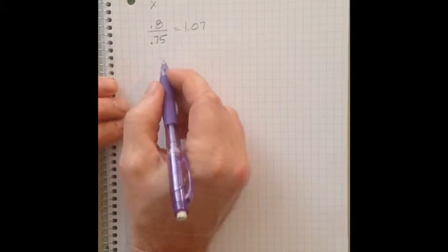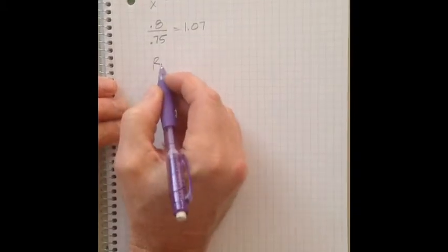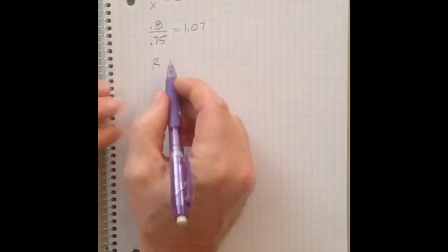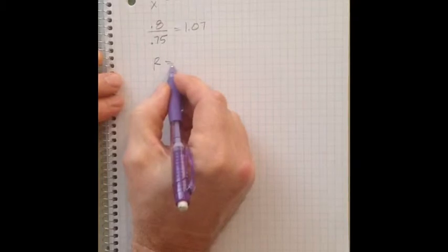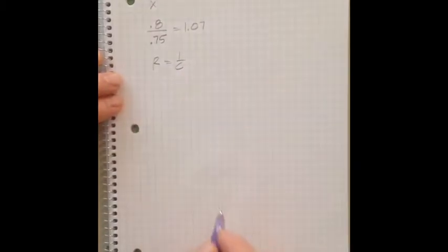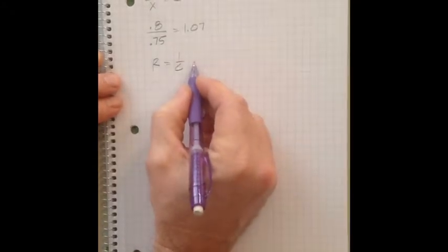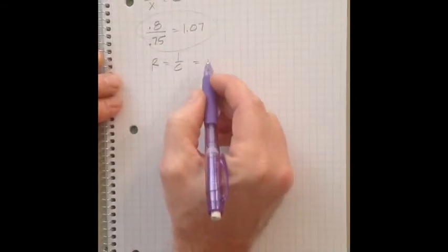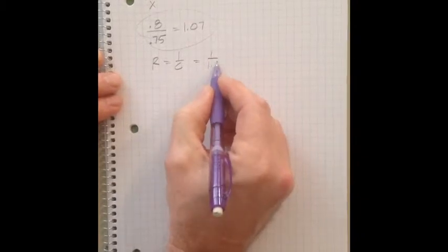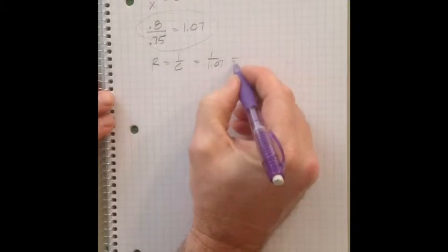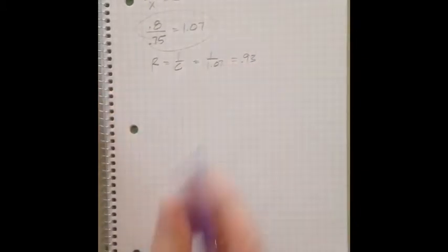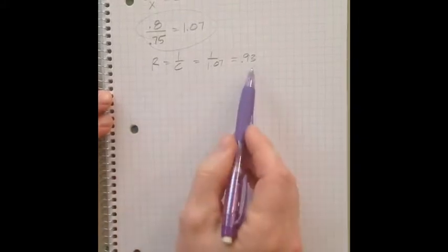I'm going to give you a couple more letters. The first letter is R. R stands for resistance, or resistance to heat flow. We use R numbers when we're using composite walls. Last week we did homogeneous walls. This week we're doing composite walls. So R equals 1 over C. For instance, in this plywood example, 1 over 1.07, I have my calculator right here, 1 divided by 1.07 is 0.93. So for this 3/4 inch plywood, the R number is 0.93.